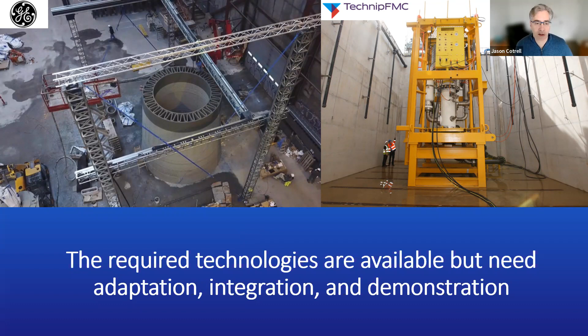The second thing we do is add multiple spheres to the system. That allows us to increase the capacity of the system. It gives us options, so we can increase the length of storage by adding additional spheres while keeping one single generator and pump turbine assembly.